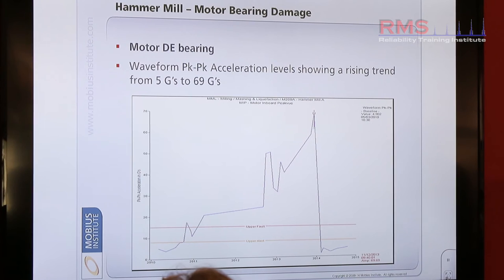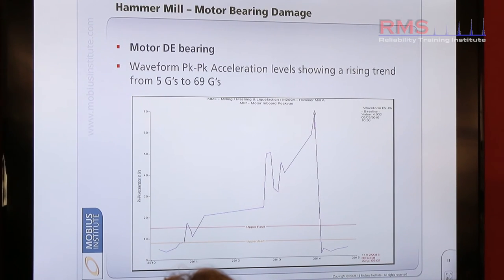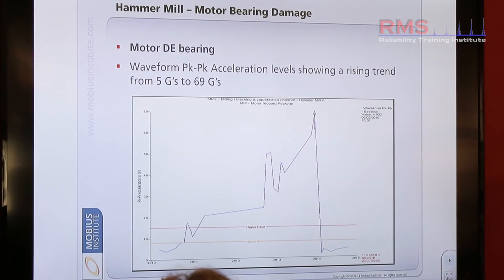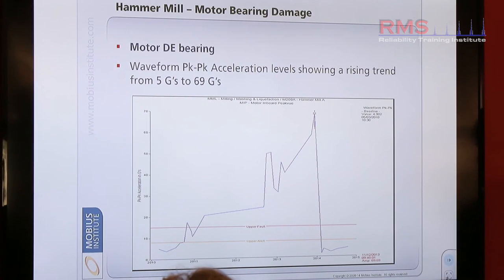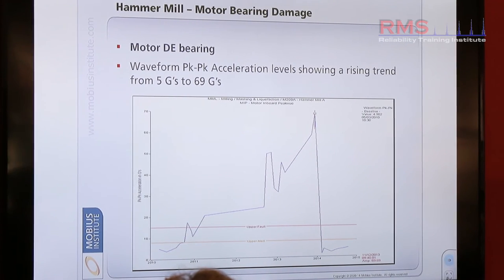Monthly vibration measurements were collected when the plant first started up in 2010, and continue to monitor this machine up to present day on a monthly basis. This trend is actually a trend of the shock within the machine — the impact force, the shocks that might be produced from a bad bearing. This is the trend of the shocks.